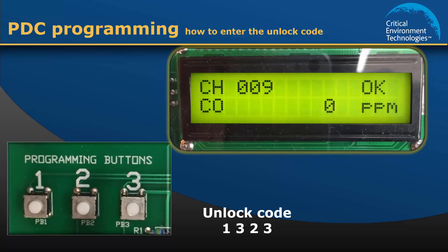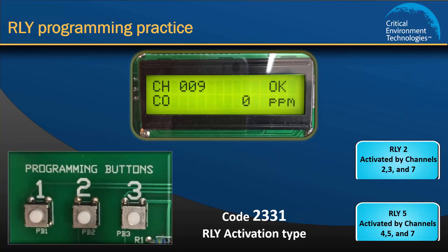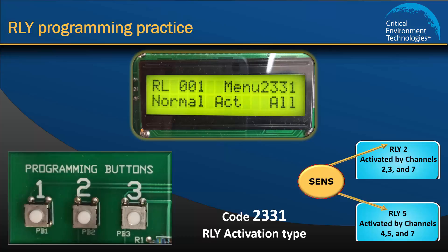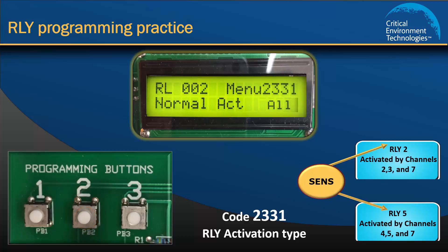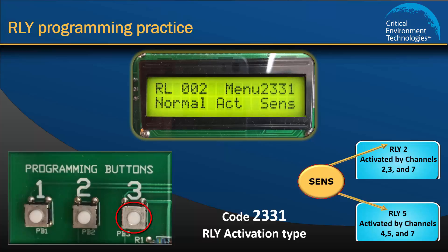Now we are ready to assign activation type Sens to Relay 2 and Relay 5. Use the programming buttons to enter the menu item code 2-3-3-1. The display will start at Relay 1 and progress through all the relays as you press the programming buttons. Relay 1 is set to All and we are not concerned with Relay 1 in this exercise, so press programming button 2 to proceed to Relay 2. By default Relay 2 is set to All, but we want to change that to Sens. Press programming button 3 once to scroll to None and then again to scroll to Sens. Save your selection by pressing programming button 2 and move on to Relay 3.